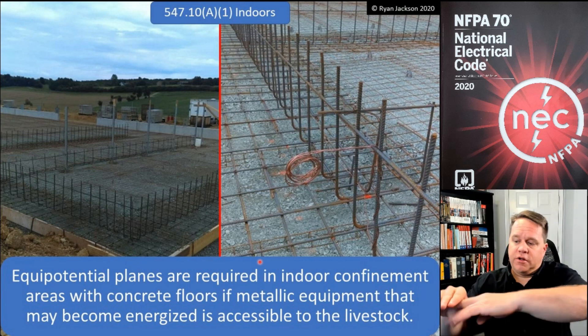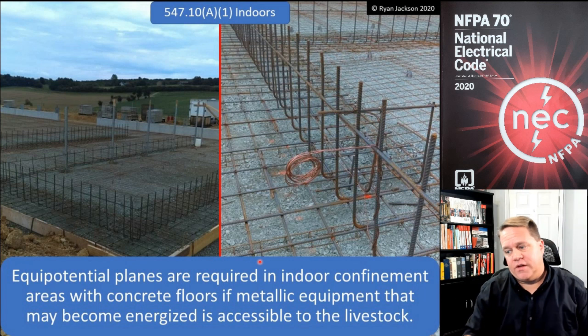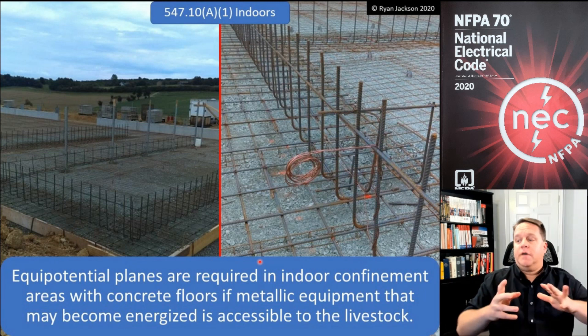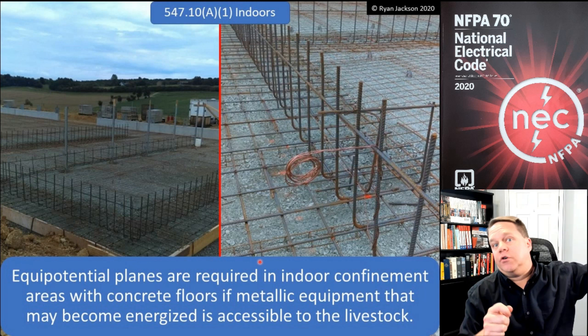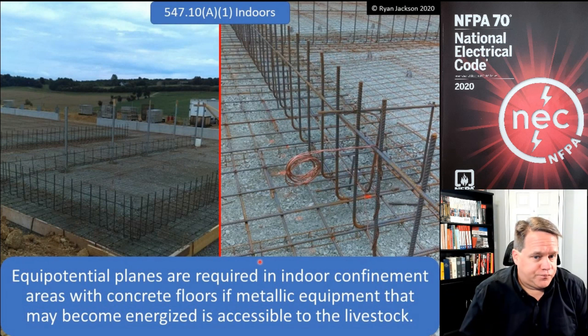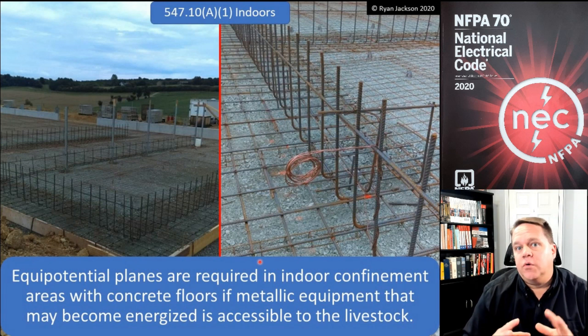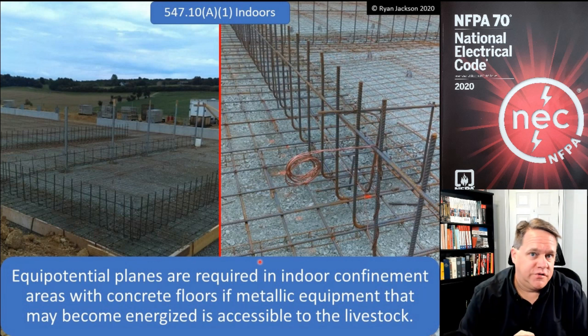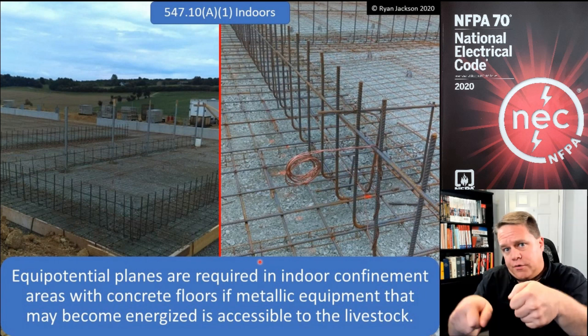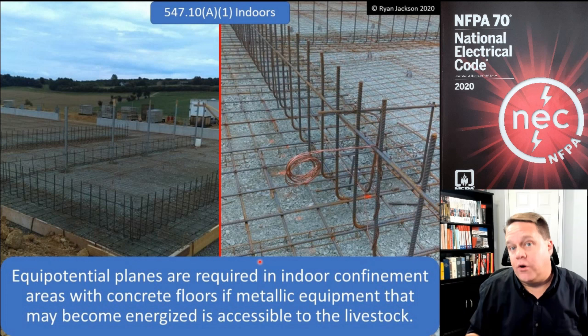To create the ramp, you take a piece of rebar and extend it out of the side of the slab, then bend it down at about a 45-degree angle and run it underground into the dirt. Let's say the concrete inside the barn is all at three volts relative to remote earth — meaning if you bury one test lead in the dirt 100 miles away (remote earth) and touch the other to the concrete, you read three volts. That's not a problem for humans, but it is for cows. You can't remove the voltage, but you can make the differences more gradual.